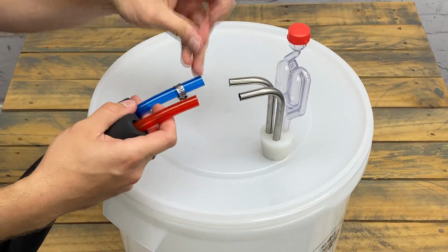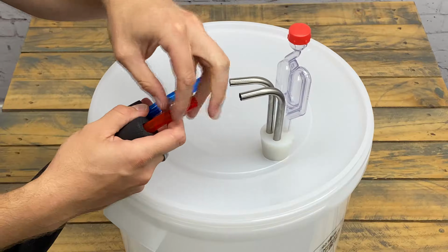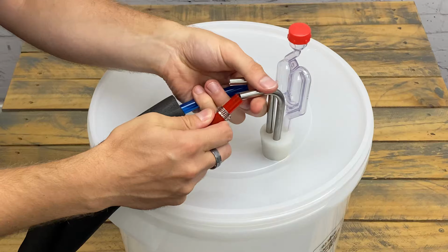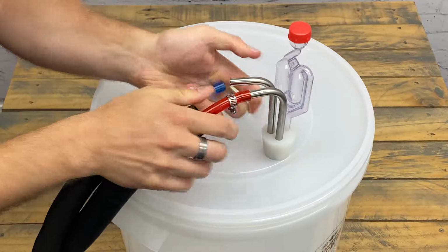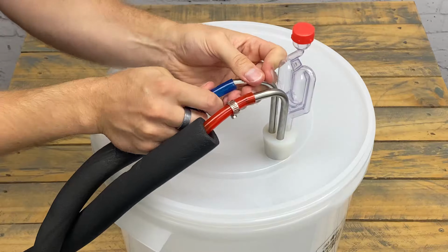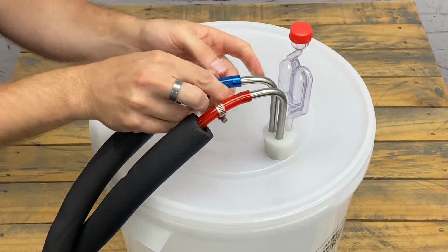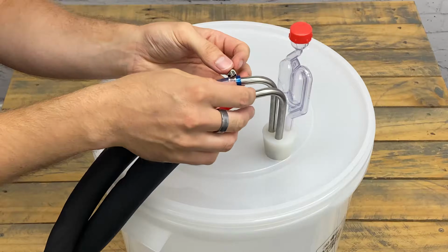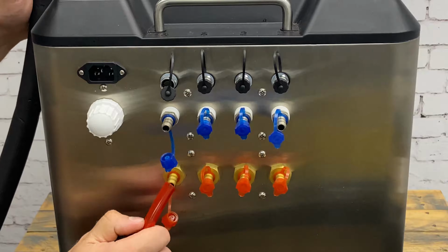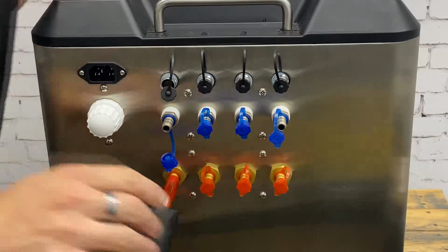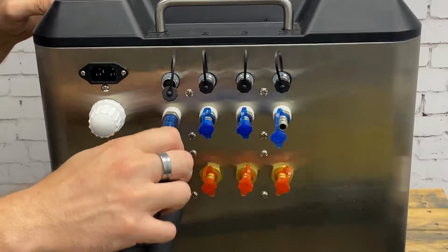Push the clamps onto the hoses and connect the hoses to the pipes of the cooling coil so there is about 1 centimeter of overlap. Use a screwdriver to tighten the clamps on the overlap section. Connect the other ends of the hoses to the channel of the glycol chiller that you want to use for the GCA.